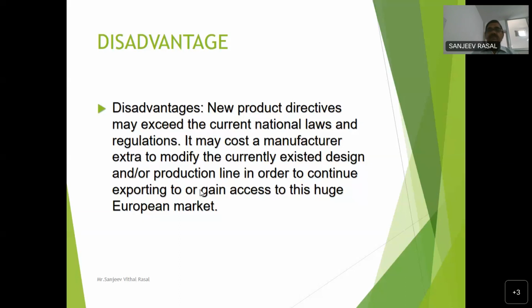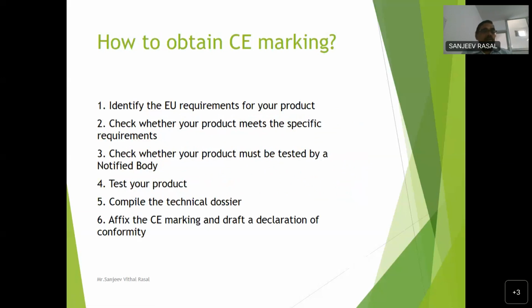Now, how to obtain CE marking? It is very essential to obtain. There are 5 to 6 steps: first, identify European requirements of your product; identify your product on the portal where you will find all the relevant lists; check whether your product meets the specific requirements; check whether your product must be tested by a notified body; test your product; then compile the technical dossier, affix CE marking, and draft a declaration of conformity.